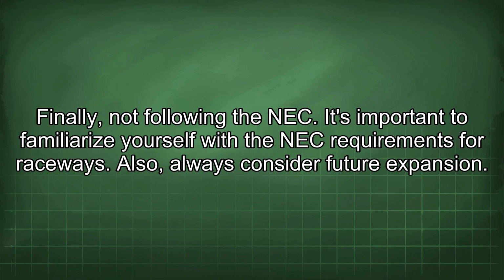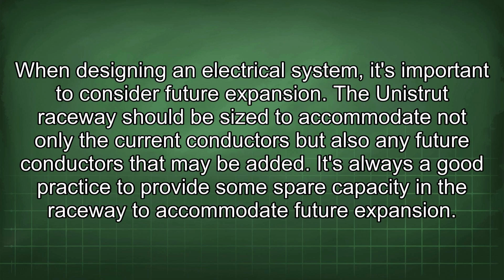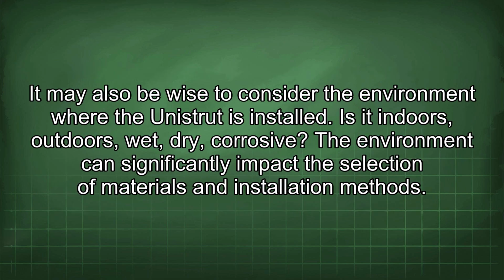Also, always consider future expansion. When designing an electrical system, it's important to consider future expansion. The Unistrut Raceway should be sized to accommodate not only the current conductors but also any future conductors that may be added. It's always a good practice to provide some spare capacity in the raceway to accommodate future expansion. It may also be wise to consider the environment where the Unistrut is installed. Is it indoors, outdoors, wet, dry, corrosive? The environment can significantly impact the selection of materials and installation methods.